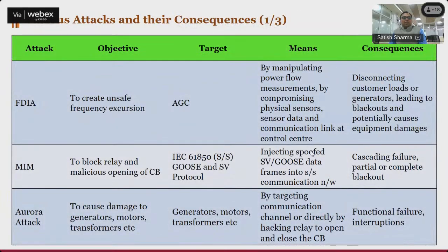Different types of attacks are there, like false data injection attacks, to create unsafe frequency excursions. The attack target can be the AGC, by manipulating power flow measurements or by compromising physical sensor data and the communication link at the control center. The consequence is disconnecting customer load or generators, leading to blackouts, or potentially causing equipment damage. So these are the attacks, their objectives, and their means and consequences.